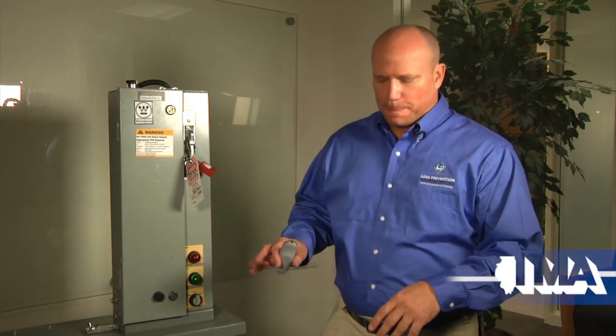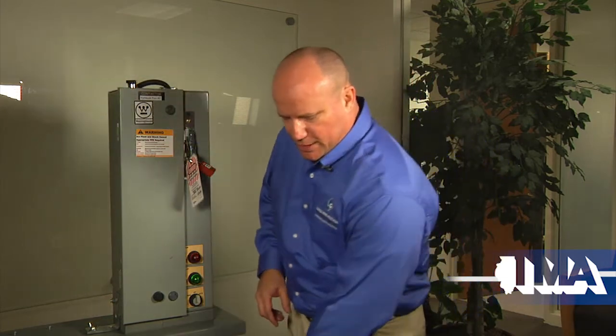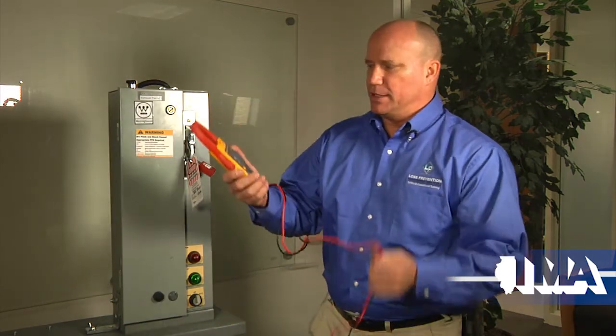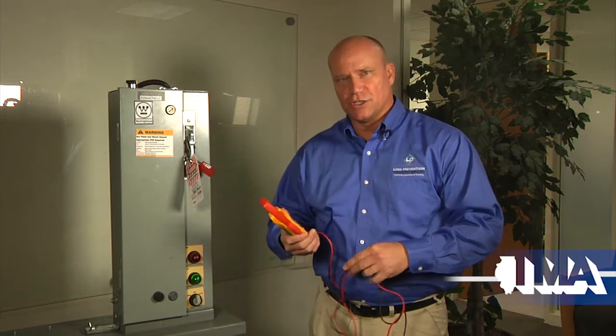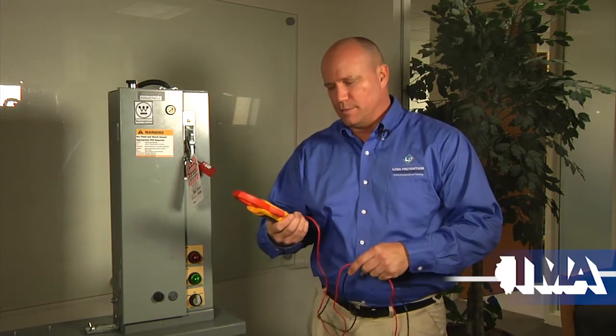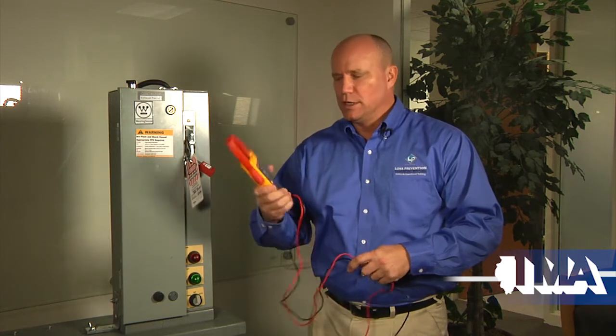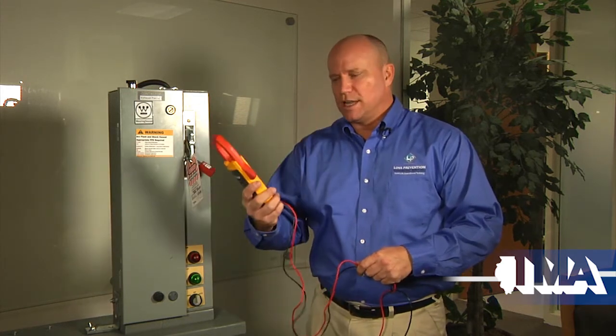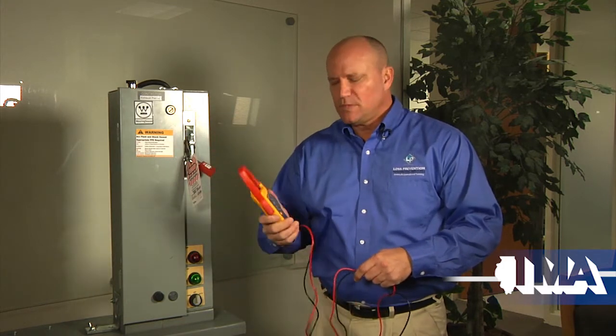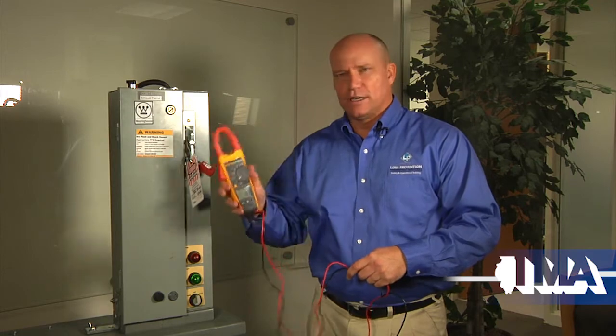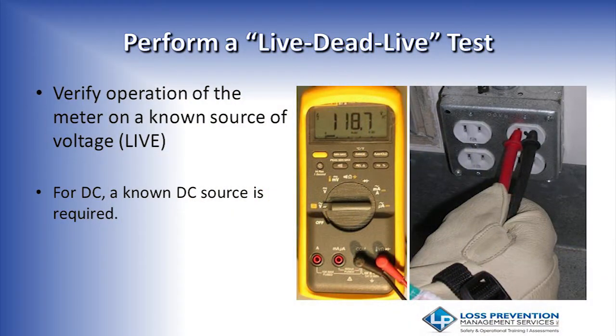Okay, as far as the tests, as I'm going through here, I'm going to walk through. You have to first find out a known live source. Typically an outlet, it doesn't have to be, but I want to make sure my meter is actually working as I expected. Now this is all after your visual verification checks. Make sure that your meter's integrity is adequate to use. Select the right voltage selection. In this case, I'm only dealing with AC. If you were dealing with DC, not only would you have to check on an AC source, you'd have to check on a DC source, like a UPS system. It would have to be both AC and DC. So in this case, which is just an AC source, okay?